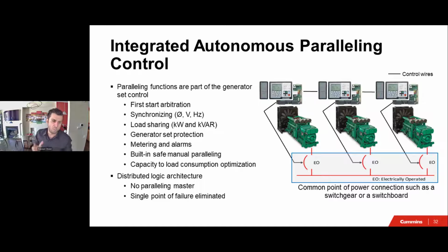You might say, well, no, I don't think so. What if I have more load than the gensets can handle? Yes, that's true. This is why you probably want to have an N+1 system, but let's say that you don't. Then you have to resort to load shedding and shed the non-essential loads. But that's beside the point I'm trying to make, and that is you will not notice a difference. The gensets will not care that they lost one. They won't freak out and go, oh, I lost one, all the synchronization is going to go out of whack. No, that does not happen. By doing so, we eliminate the single point of failure. If I have 7 gensets and I lose 1 or 2 or 3, the remaining just continue operation without a problem.